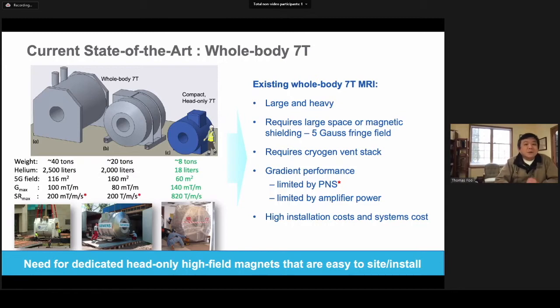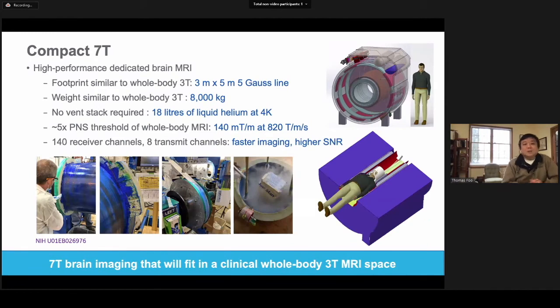This points to a need for dedicated head-only high field magnets that are easy to install and also lower cost. This leads to our project, which has been funded by the Brain Initiative. This is a compact 7T magnet and system that we're building. This system is about the same size as a whole body clinical 3T scanner, occupies the same footprint, and has about the same weight. The only exception is that this is cryogen free, with only a closed loop system with 18 liters of liquid helium at 4 Kelvin. In addition, because it's a head-only scanner, it's able to achieve 140 millitesla per meter at 820 Tesla per meter per second slew rate, much faster than whole body systems. Also, because it has 140 receiver channels and possibly 8 transmit channels, it's able to achieve faster imaging and higher SNR.